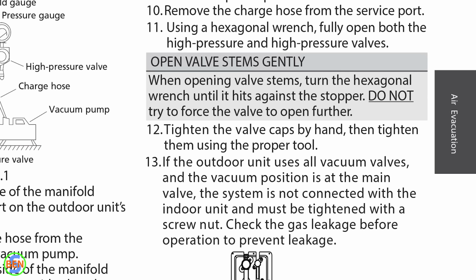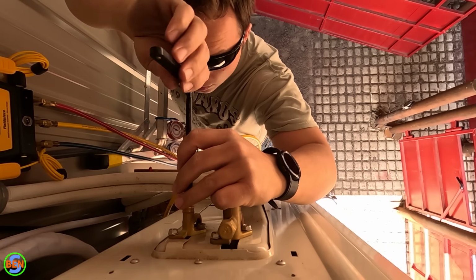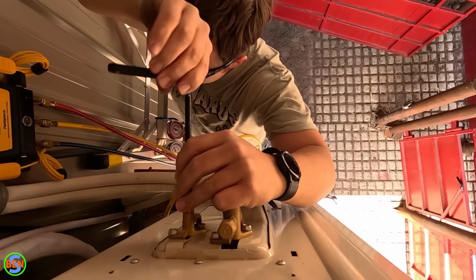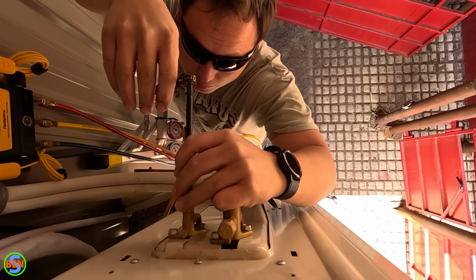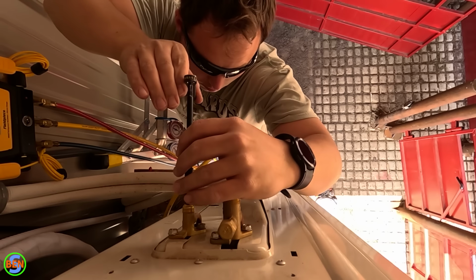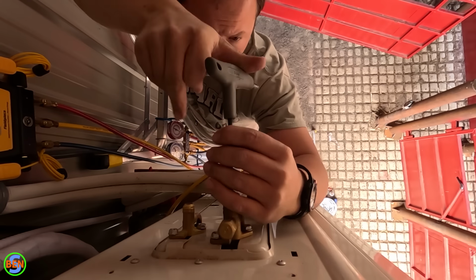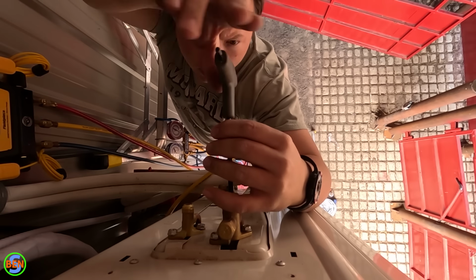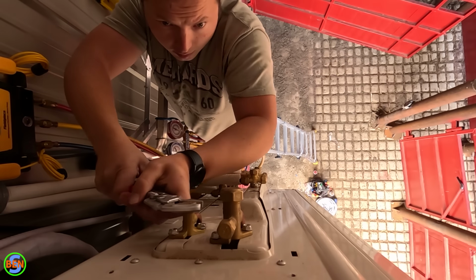The instructions will tell you exactly how they want you to do this. Sometimes there's a particular sequence that they want you to go through, but typically it's just going to be a matter of opening the high side valve, and after that is fully opened, then opening the low side valve, and then make sure all of the caps are in place and tightened over those access valves.